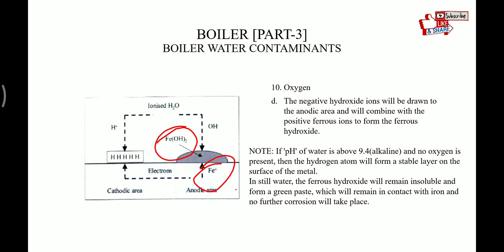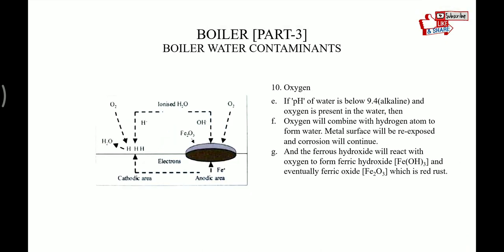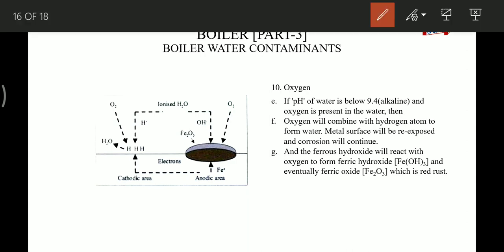If the pH of the water is below 9.4 and oxygen is present, then oxygen will combine with the hydrogen atoms to form water, the metal surface will be re-exposed, and corrosion will continue. The ferrous hydroxide will react with oxygen to form ferric hydroxide, and eventually ferric oxide, which is red rust.